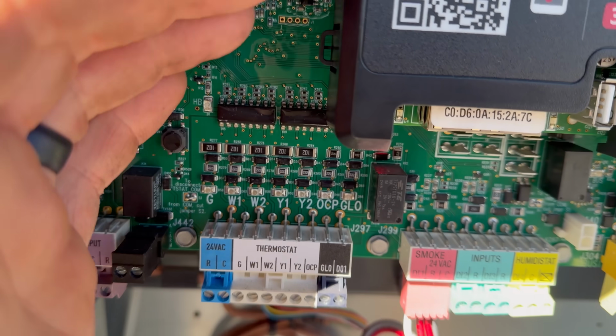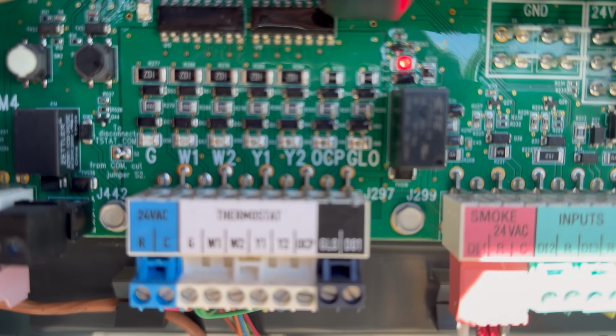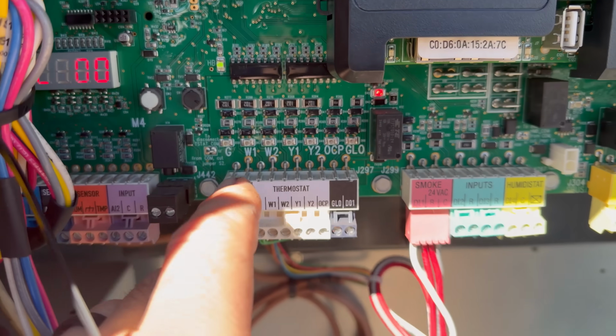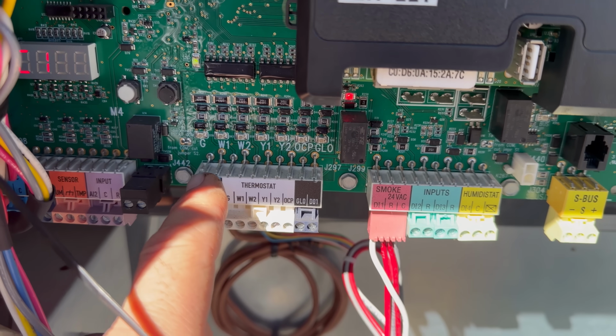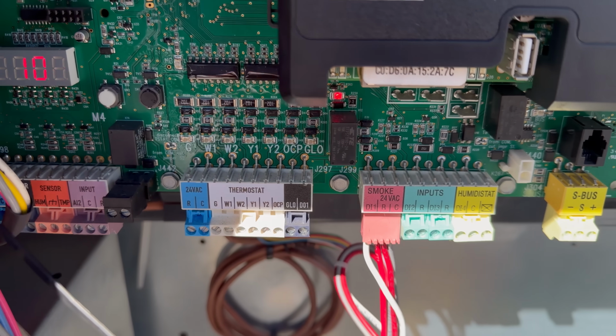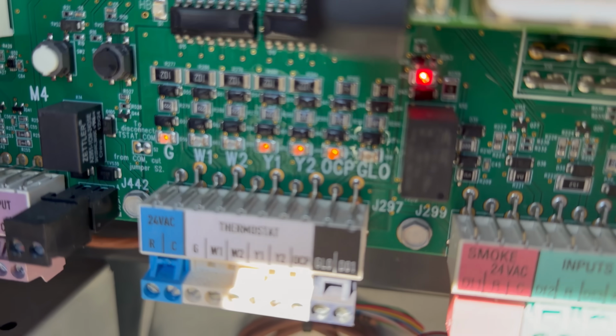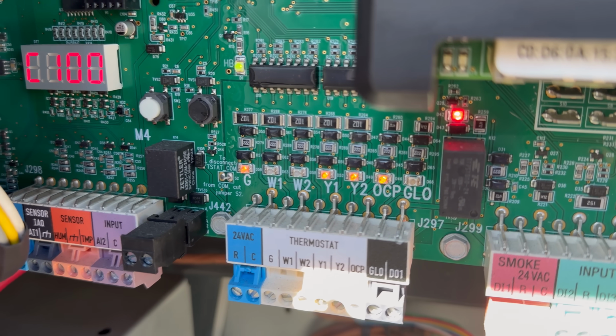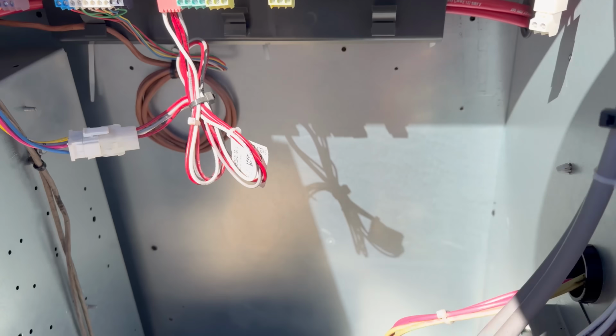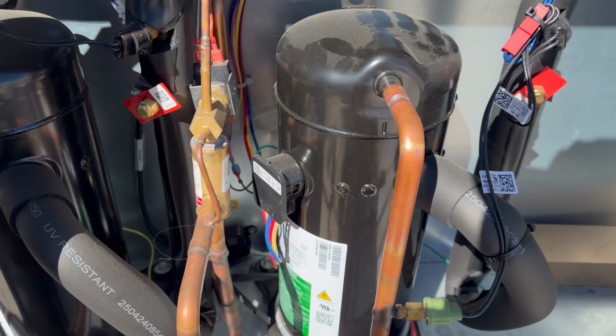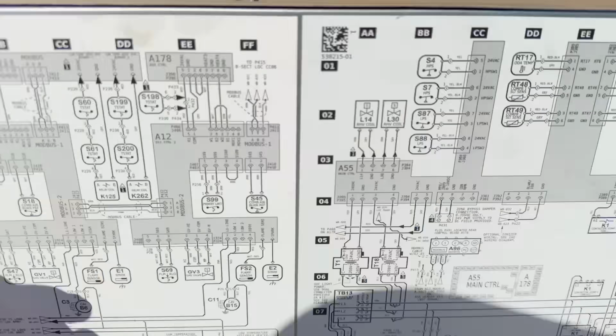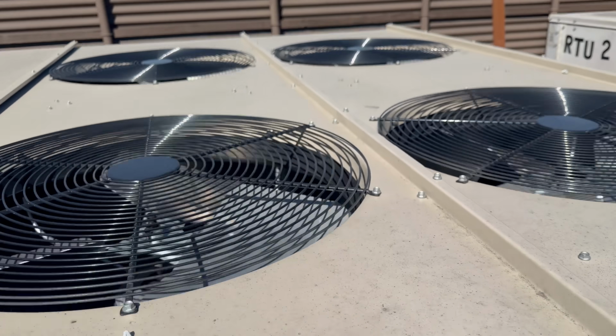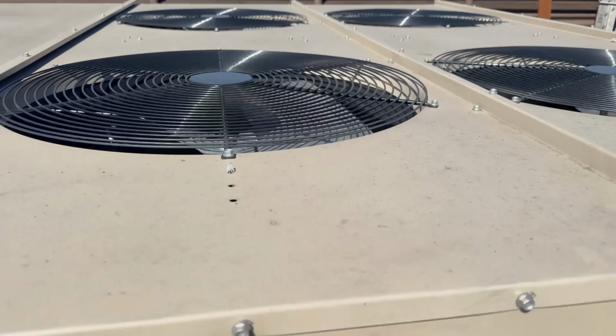If I can get you guys to see here. For whatever reason, I hate these things because they don't show accurately, but I've now got a call for G, Y1, Y2, and OCP. There you go. Now you can see it. So we have a full call and all 3 compressors are running, but we're still gonna profile everything just to check it out. Let's see if our condenser fan motors are all running. All the condenser fan motors are running. They're going in the right direction. Good airflow across the condensers.